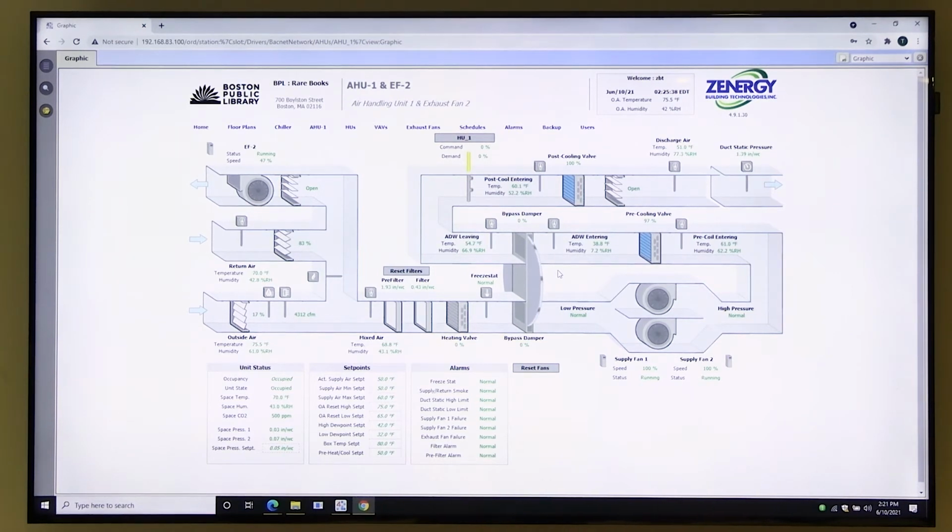The next thing we see here, there's the freeze stat. When it's the dead of winter and it's 0 degrees outside, hopefully you don't have any issues with this, but if you were ever to have outside air come in and have a heating issue, say the boilers weren't running, this is just a safety to keep things from freezing. It'll shut down the unit so we don't have water all over the floor and cracked coils and stuff. So this is just a typical safety whenever you have a hot water coil.